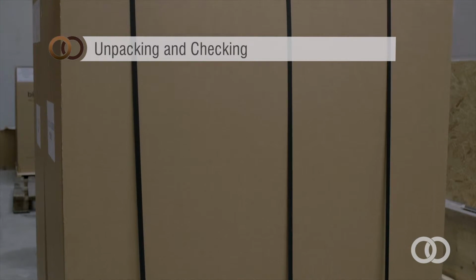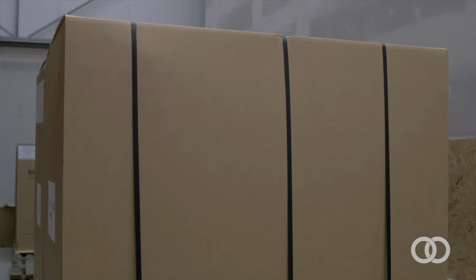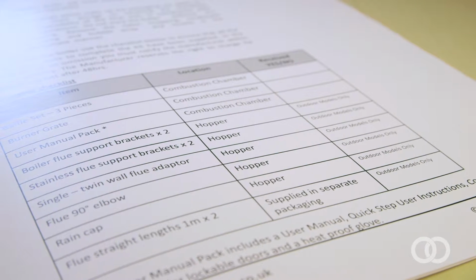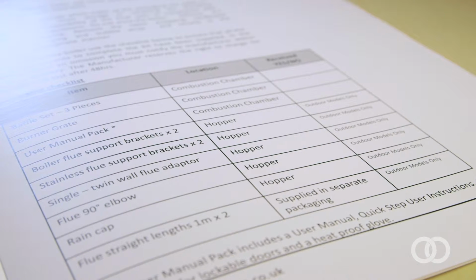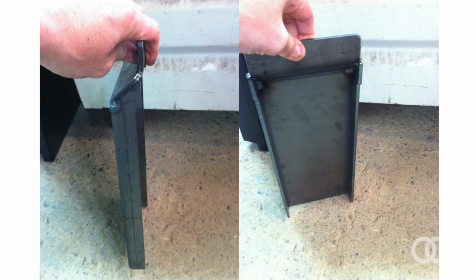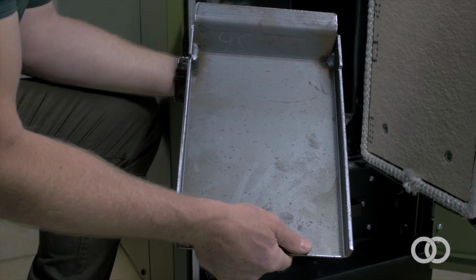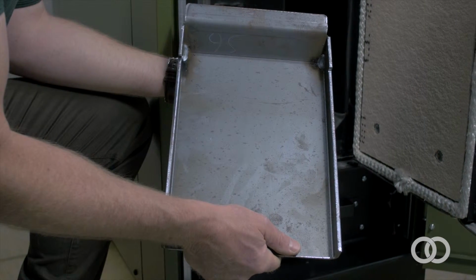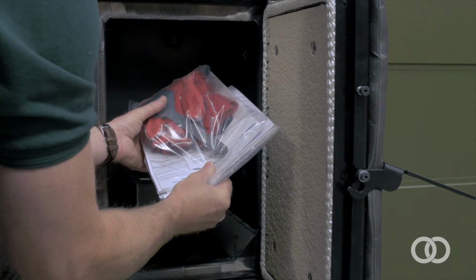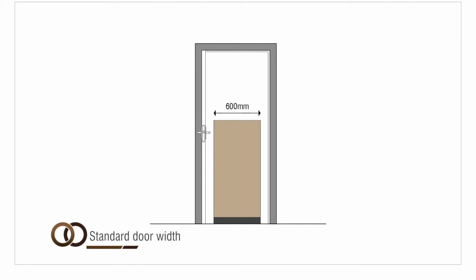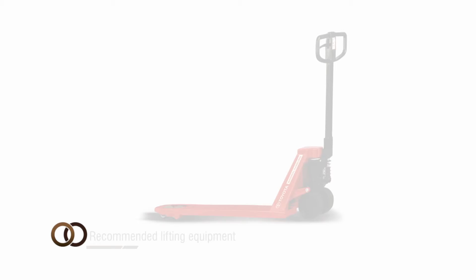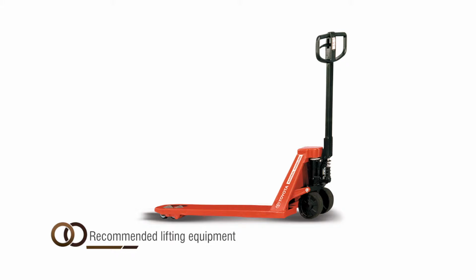Unpacking. The W-Compact iGen is supplied on a single pallet, and the materials which make up the packaging are 100% recyclable. Check the unpacking checklist in the manual to ensure you have all the required components. 2 baffle plates on a 28 kW boiler, one baffle plate on 15 and 18 kilowatt models, user manual pack, burner grate, etc. All 15 to 28 kilowatt domestic boilers are designed to fit through a standard door width. However, they do need careful handling, and you will need manual handling equipment. For example, the 28 kilowatt model weighs almost 200 kilograms.